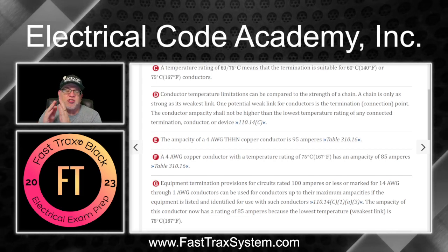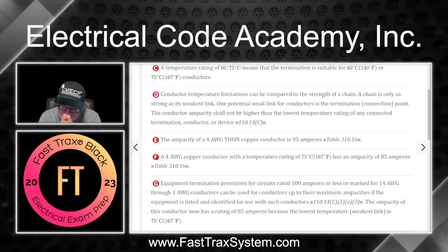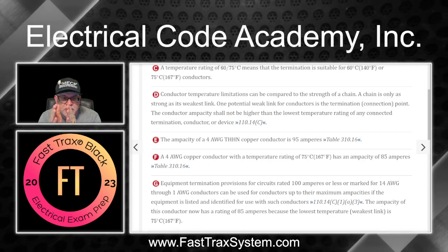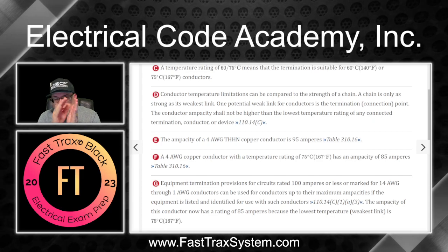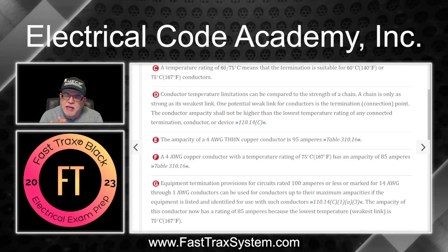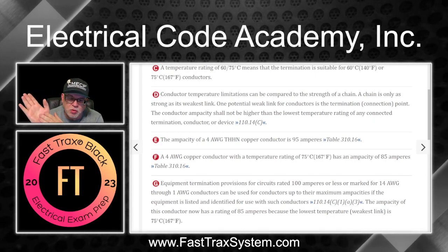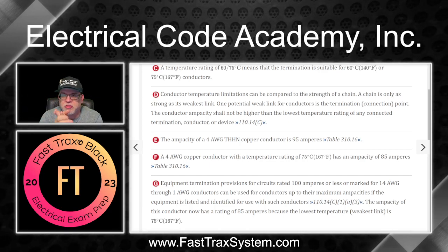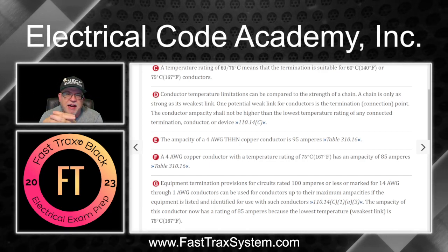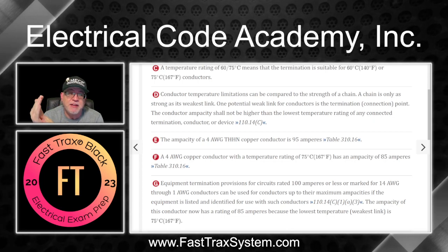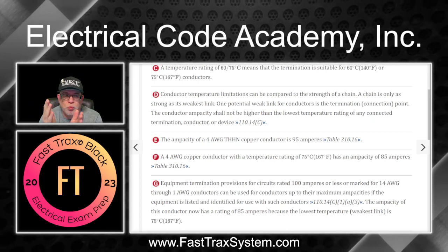So that just serves to remind you that when you're looking at an installation, you need to look at the rating of the terminals, the rating of the conductors that you're using, and the rating of the end load, whatever equipment it's terminating onto. If all of those are 75, it really wouldn't matter if it is 100 amps or less, or 14 through 1 gauge.